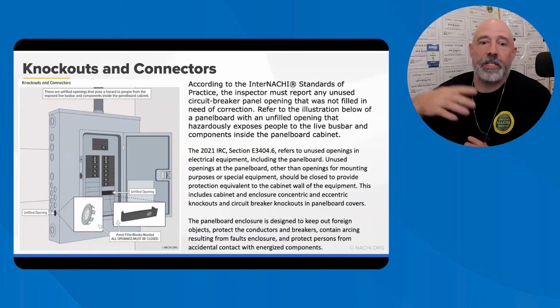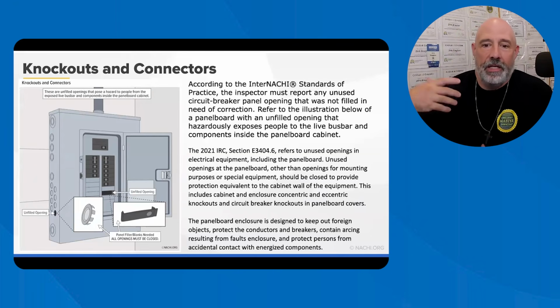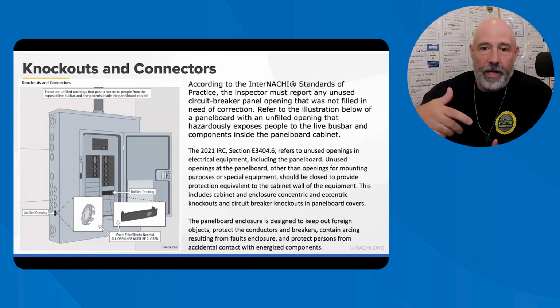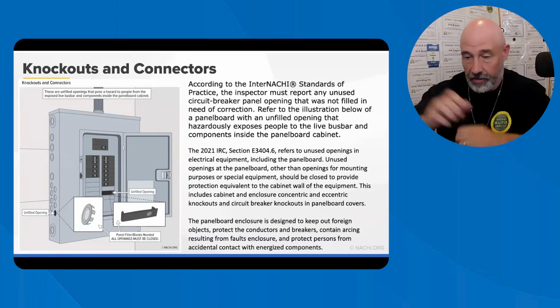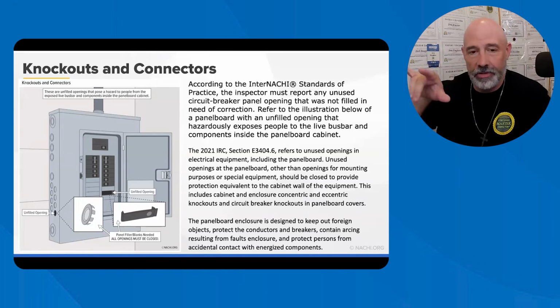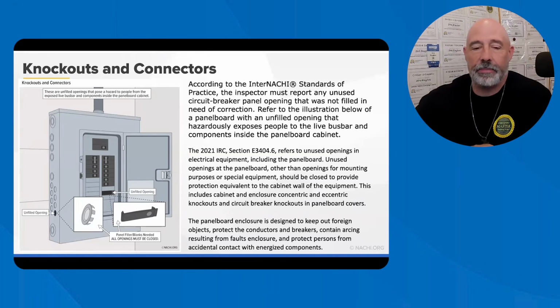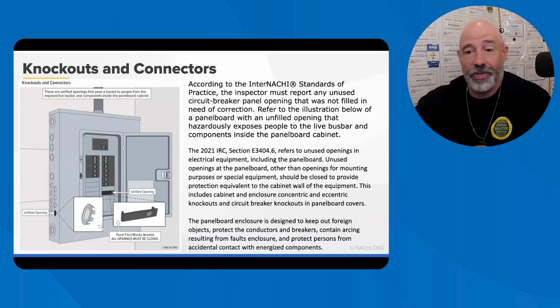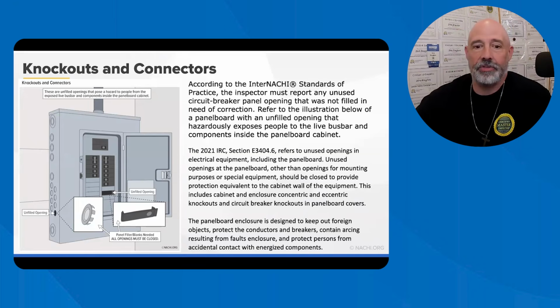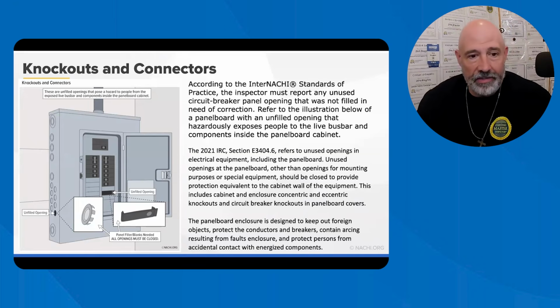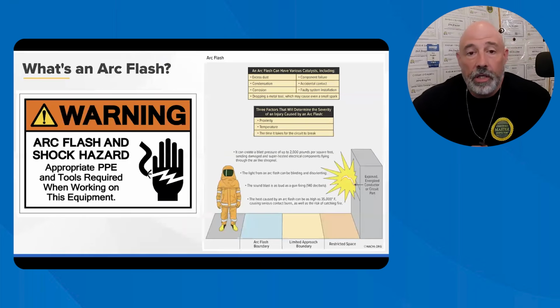So this section is not intended to be applicable to the holes provided for fasteners for mounting purposes. So when you're hanging the panel board, those little tiny holes are not such a big deal. The big knockouts where you can stick your finger in, that's a big deal. So make sure that you're calling that stuff out. An arc flash. Now, this is where it gets scary. And I'm not going to lie to you.